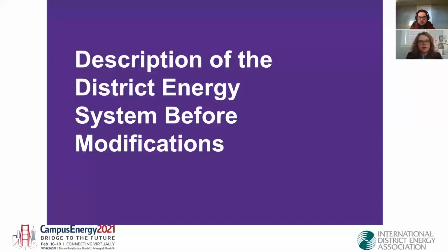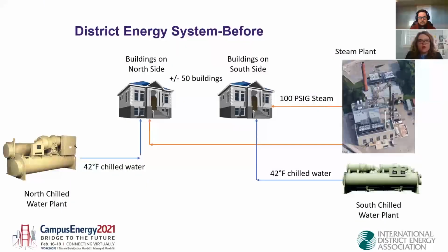Thank you, Evan. So we have two chilled water plants on the campus, the North chilled water plant and the South chilled water plant, and we have one steam plant. All buildings are supplied by this one steam plant, so there's more or less 50 buildings. The South chilled water plant supplies the buildings on the south, while the North one supplies the buildings on the north side. We have steam supplied at about 100 PSIG to every building.